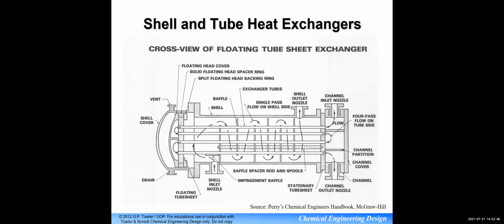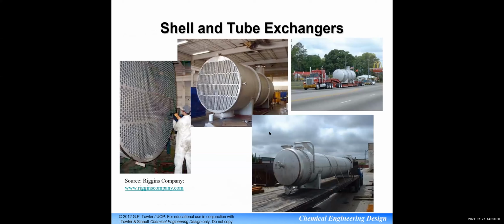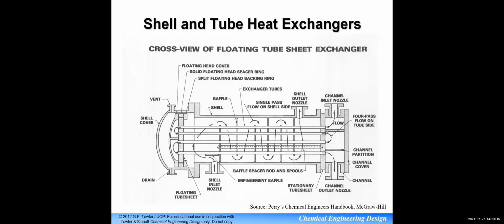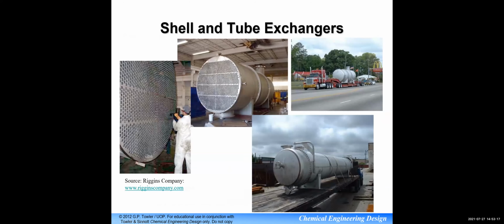The baffle will help your flow to be redirected so that it can be distributed evenly into your heat exchanger. This is the shape of an actual heat exchanger, kind of a big one, but you can see here the spacers. These are the dividers that are introduced into that exchanger. So there are several tubes that go in, probably on another side there will go back to that side, and then you will have a 4 pass heat exchanger.